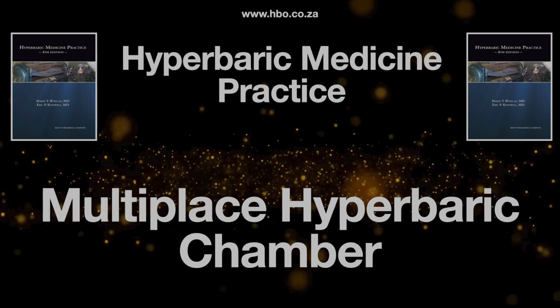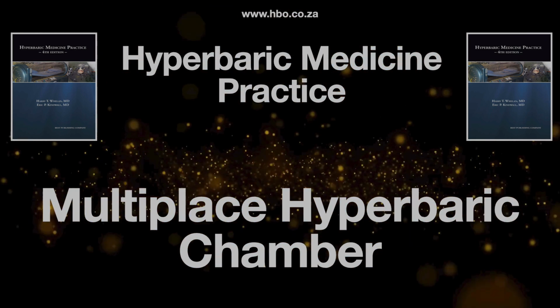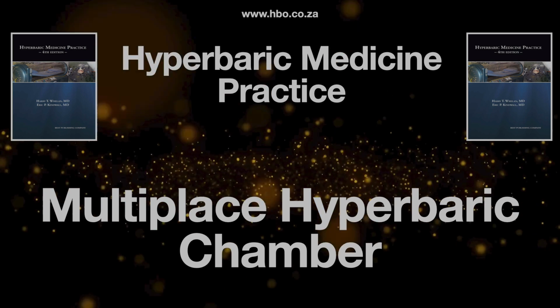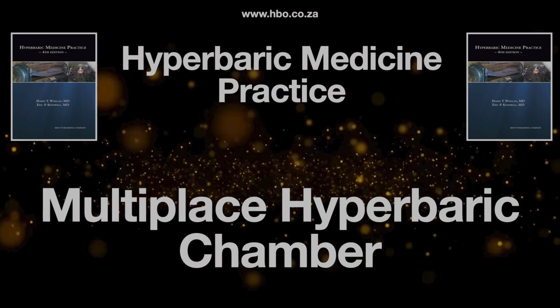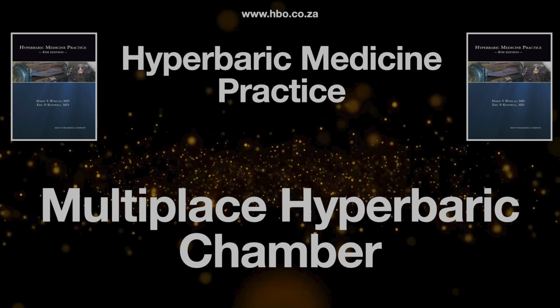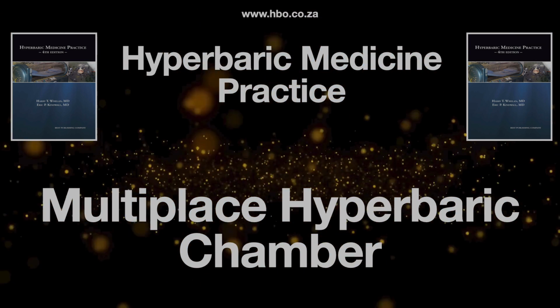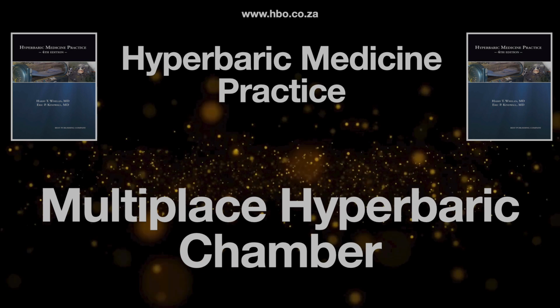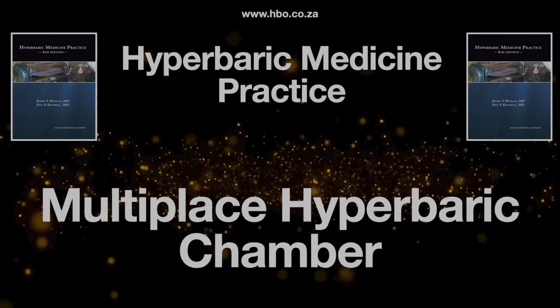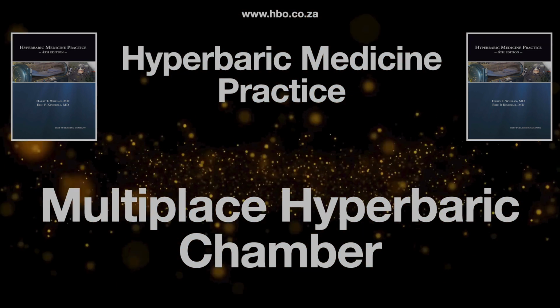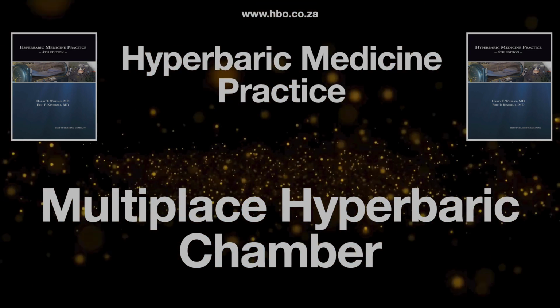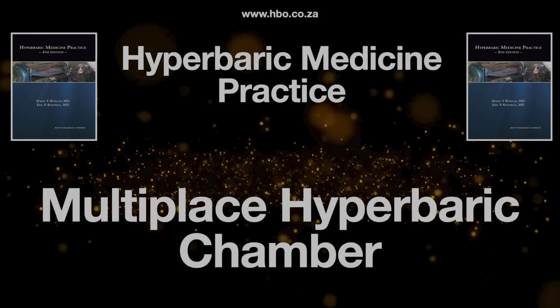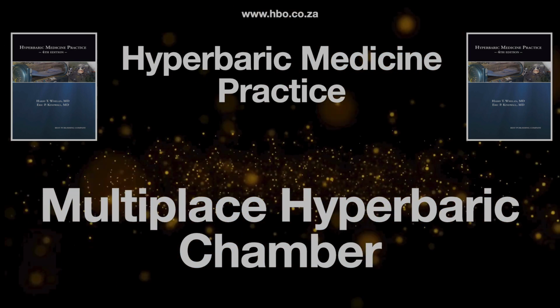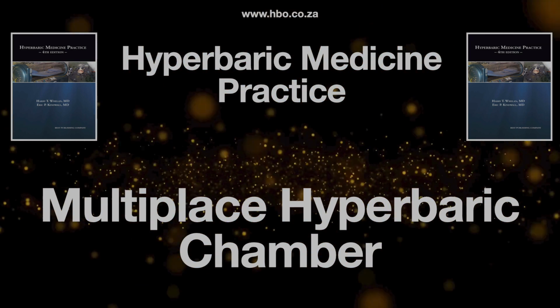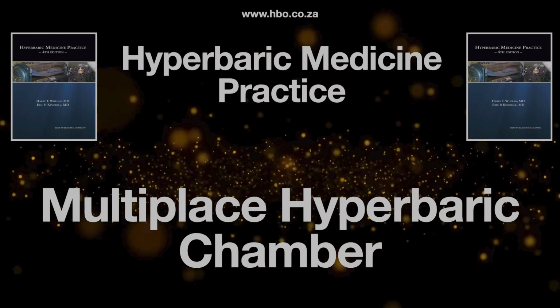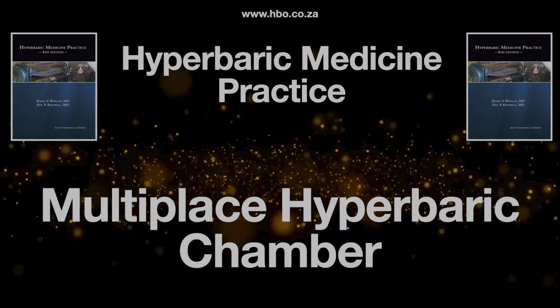When we talk about a multiplace hyperbaric chamber, the first key thing to understand is these aren't just off-the-shelf pressurized rooms. In Europe, they're rigorously certified Class IIB medical devices, stamped under Directive 93/42 EEC. Guidelines like MEDDEV 2.4/1 ensure they meet incredibly high standards for safety and performance, impacting everything from materials to manufacturing. You'll always see the European community marking on them, backed by a huge technical file manufacturers have to keep. So, super regulated from the ground up in Europe.